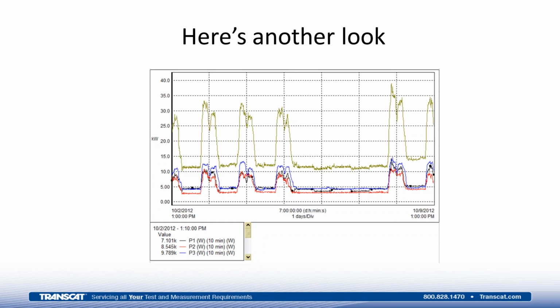The problem is if that capacitor bank is not working properly and stays on, for instance, all the time, when your motor turns off, you create a leading power factor, which is just as bad as the lagging power factor. So capacitor banks are typically either sized way under the total load, allowing for some power factor to still exist under full operation but compensating for lighter operation, or they're dynamic, which allows them to add or subtract capacitance as the loads in the facility change. In many instances, we have found these capacitor banks were installed years ago, not checked, and as a result were misoperating, actually costing the customer money instead of saving the customer money, which is the purpose of the capacitor bank that is installed in an industrial sector. Again, I hope that answers the question.